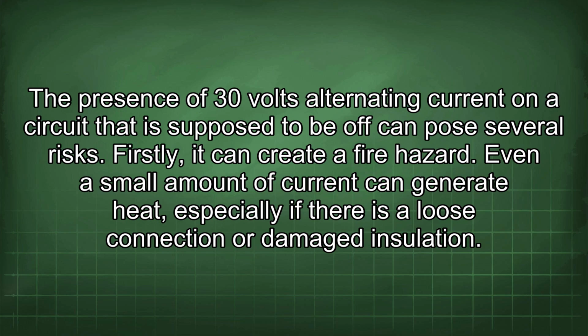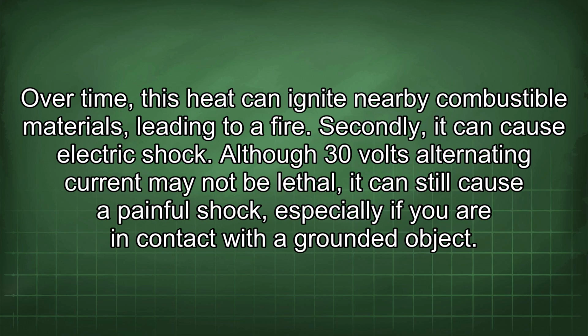The presence of 30 volts alternating current on a circuit that is supposed to be off can pose several risks. Firstly, it can create a fire hazard. Even a small amount of current can generate heat, especially if there is a loose connection or damaged insulation. Over time, this heat can ignite nearby combustible materials, leading to a fire.